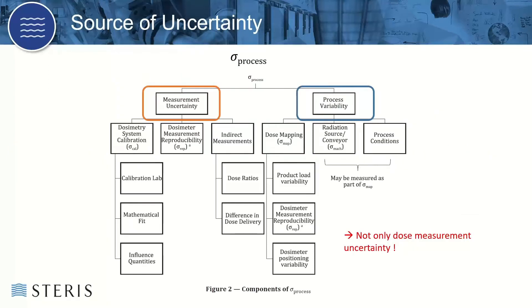What are some of these sources of uncertainty? This is Figure 2 taken from ISO 11137 Part 4. The takeaway here is that process variation — sigma process — is comprised of both measurement uncertainty, which is an output uncertainty, and process variability, which is determined from assessments completed to establish the routine process and our routine process input. The main point is that it's not only measurement uncertainty that you have to consider when setting up your process.